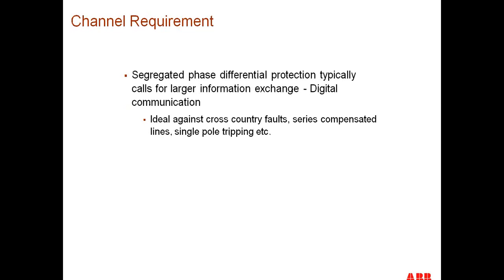Segregated phase protection calls for a large information exchange. Segregated phase protection means I'm keeping each one of the phases separate and transmitting that phase information for each phase separate from each other. The other method, of course, would be to use a combined sequence component, which means I do similar to what we did in HCV, and I combine all three phases together in some way and transmit one composite signal over the line, and then do an operation on that signal.